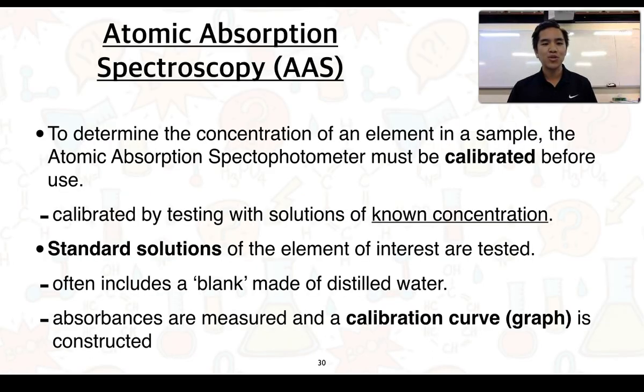If we want to determine the concentration of an element in a sample, the atomic absorption spectrometer or spectrophotometer must be calibrated before its use. To do so, we calibrate it by testing it with solutions of known concentration. In other words, we use standard solutions of the element of interest. This often includes a blank, which is just made up of distilled water, and this just confirms that there is no contamination of our water to prepare the solutions.